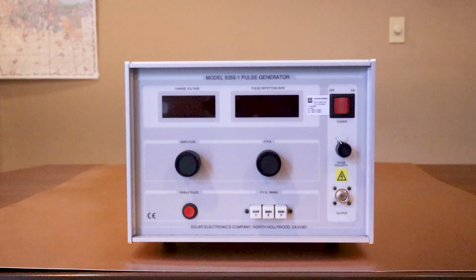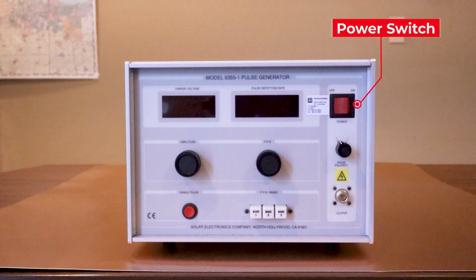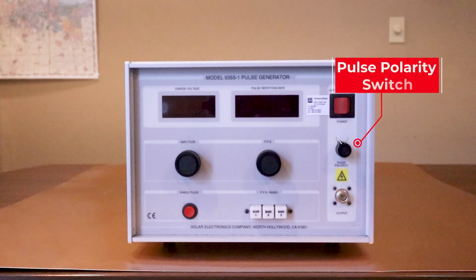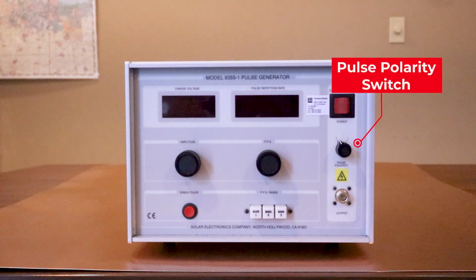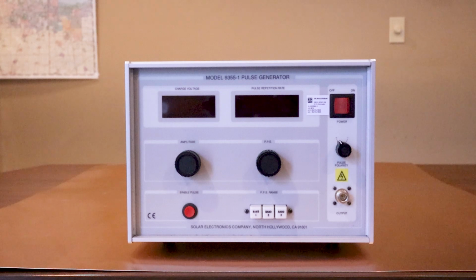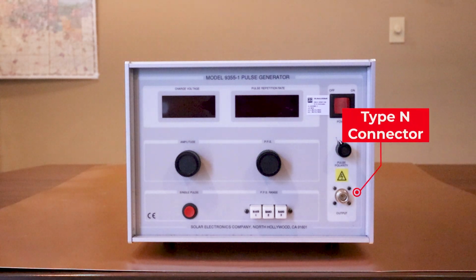Looking at the right side of the unit, in the upper right hand corner, you will see our power on switch. Just below that, you will see our polarity switch. You can see we have it set to the left as positive, and you can just turn it to the right if you need to go negative and adjust it accordingly. Just below that, you will see the type N connector, which is our output connector, and that's going to our injection device.